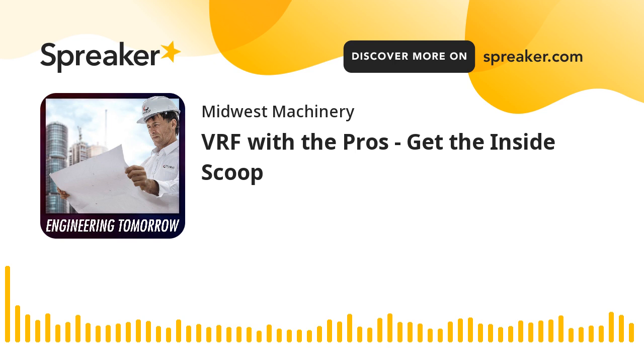If I can piggyback off of that, it really comes down to working hand in hand with your contractor, and that's where I've found a lot of my success. And looking forward to the success here with Midwest Machinery is making sure the contractor's educated, that they're purging nitrogen, that they're making clean brazes, keeping that system really airtight. The triple evacuation process, as well as pressure testing, is going to be our crutch for detecting leaks in the system before we fully charge that system. So as long as we're holding that charge and we get that system really clean, you can feel confident about the leak potential being low.